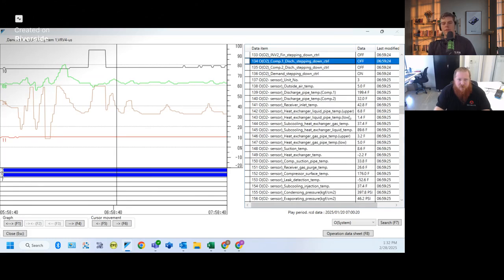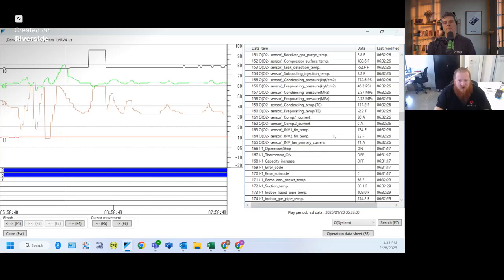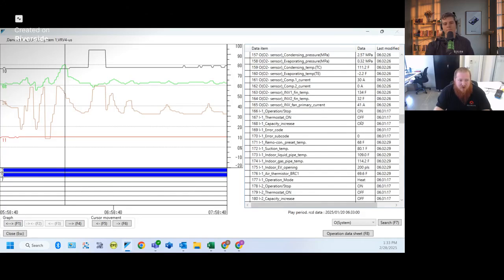So the second thing is we just found our second outdoor unit. So we got a little discrepancy on our discharge pipe temperatures, right? It's still warm, but it's not spiking like the second one. I'm gonna skip over the other section of the outdoor here, and go to the indoors to see what we're kind of looking at. I want to see in the range that we come out of our safety. I want to see what we have actually calling, right?